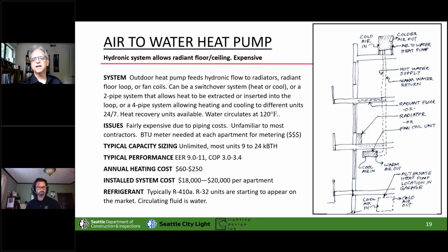And you could do a 4-pipe if you have a really generous budget. It is worth saying that 4-pipe also gives you some neat energy recovery things, but only on big buildings that have more of a central plant style heat recovery chiller thing going on. Heat recovery chillers are a relatively new technology that we'll be talking about lots in the future and lots on the upcoming few slides. But they're basically a chiller that can run backwards as a heat pump and provide heat instead. So think of your very normal air-cooled chiller, and then picture that running its refrigeration loop backwards to put heat into the building instead. And that is a heat pump chiller.